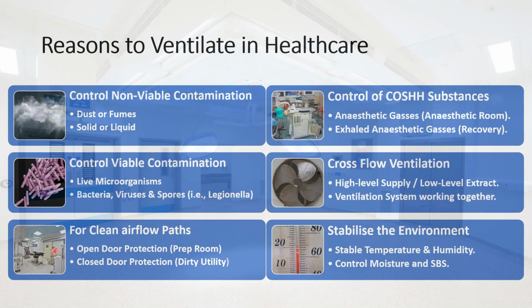The third reason is for clean airflow paths. I'm going to touch on this a little bit in the next couple of slides. Open door protection for clean spaces. So when we talk about layup prep rooms, that's the cleanest part of the operating theatre, in more cases than not. And then the dirty utility is the dirty space. So if the dirty space was adjacent to a clean corridor, we would keep that under minus 5 pressure. So when the door opens, we wouldn't get any backwards flow coming into that room. So everything that's nasty in the dirty utility, we're keeping it in that space. And then equally with the prep room, if we're opening packs up, we want to make sure that the pressure cascades out from the clean to the less clean areas.